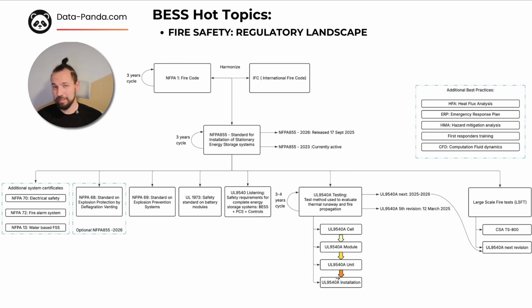We'll talk about UL 9540A in the next videos, because there will be 3 or 4 slides only regarding UL 9540A, as it's the most critical component. And this test method evolves roughly every 3 to 4 years, with the 5th revision being published in March 2025. There will be new revisions soon to accommodate large-scale fire tests. And right now large-scale fire tests are very much discussed. We'll also discuss them, but the idea is that we try to accommodate real-world fire scenarios to validate safety design and fire mitigation strategies. Right now there is only one standard, a Canadian standard from CSA, CSA TS800, which provides guidance for large-scale fire testing.